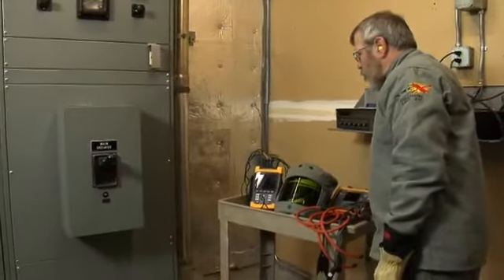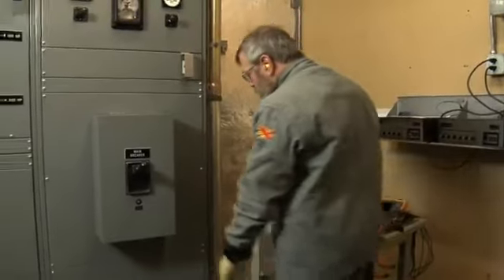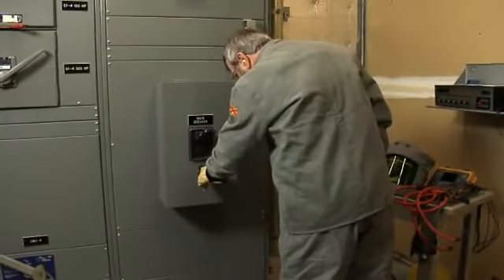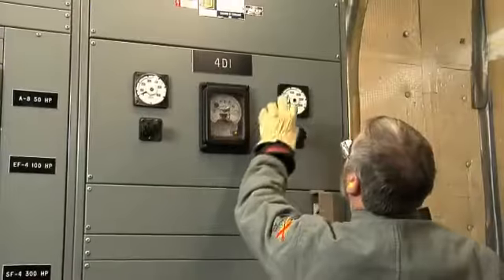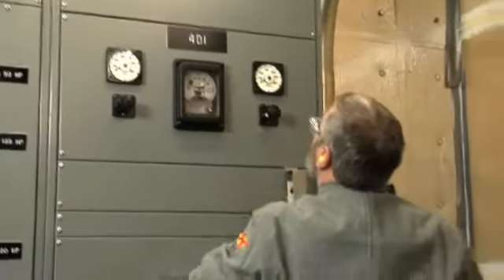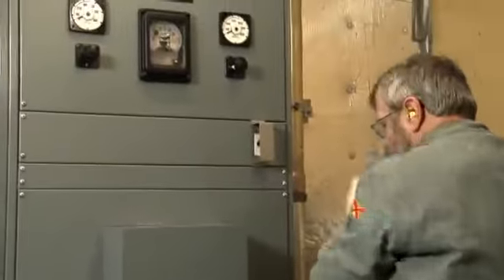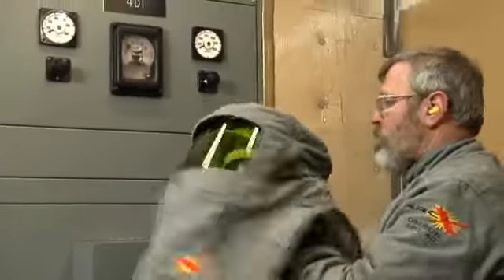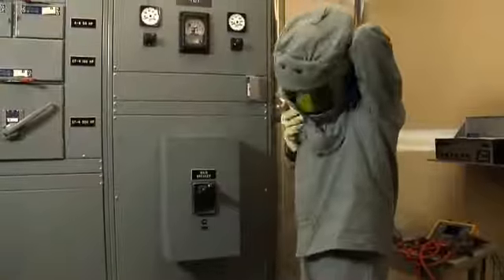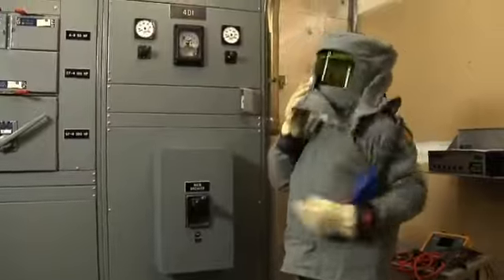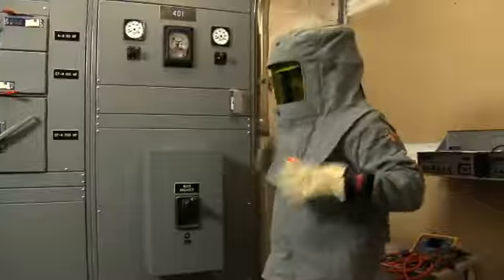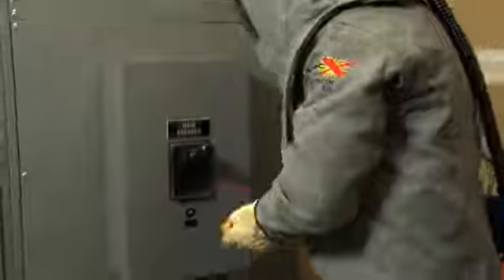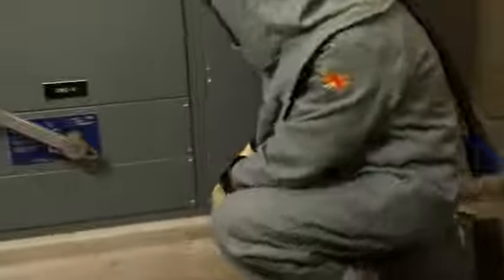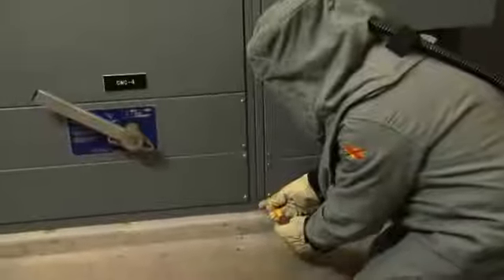When you are working with voltages of greater than 50 volts, it is extremely important to use the proper personnel protective equipment, or PPE. The PPE you choose should be based on the arc flash warning label found on the equipment, or the tables in NFPA 70E. To remove a cover downstream of the 480 volt breaker, this worker has chosen hazard risk category 4 clothing and class 0 voltage rated gloves. Connecting at the service is tricky. Make sure you are using your voltage rated tools.